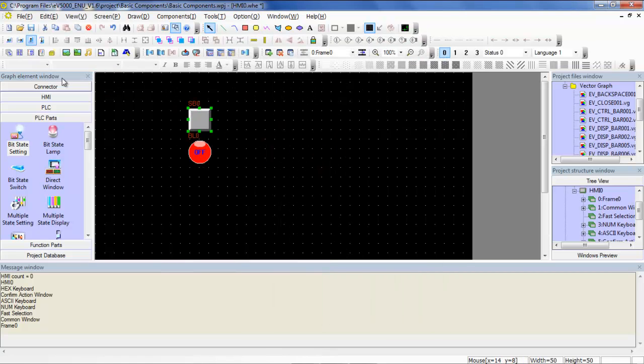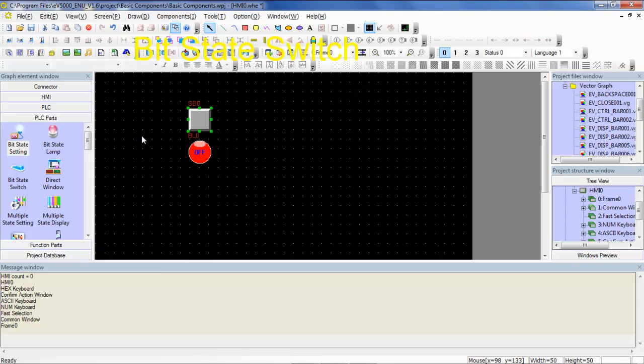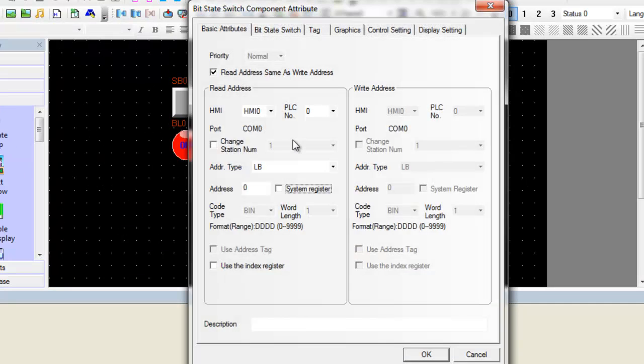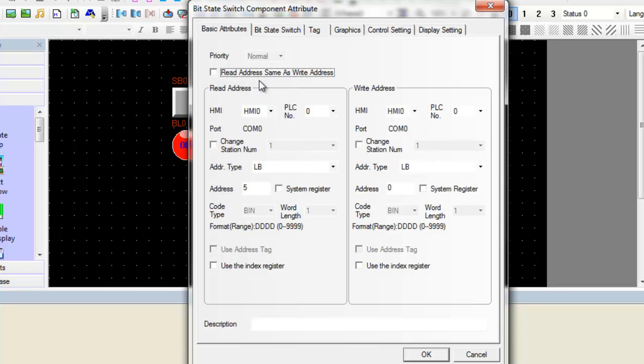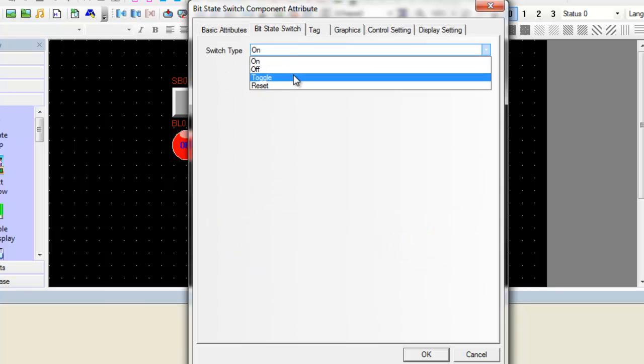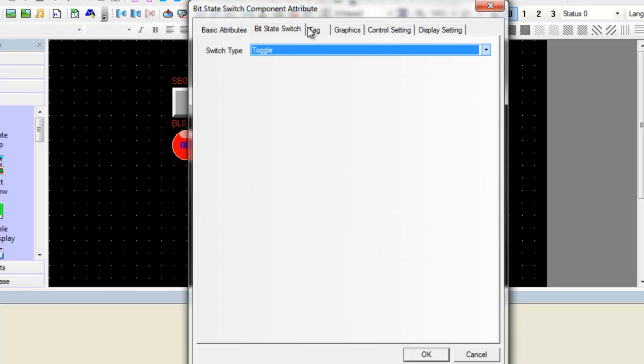Finally, our last component that we will be covering today is the bit state switch. The bit state switch is a combination of the bit state lamp and the bit state setting component. It will indicate the on-off status of a PLC bit register and also define a touch area that when activated may change the status of a designated bit register. The input address is the bit address of the PLC register which controls the switch's state, and the output address is the bit address of the PLC register whose on or off state is controlled by the switch.